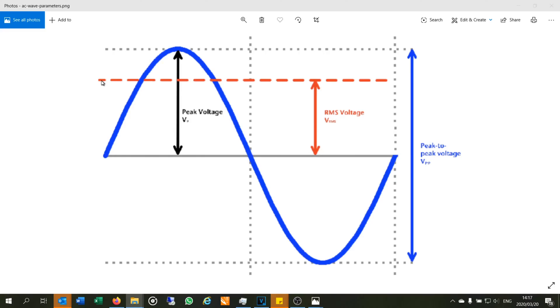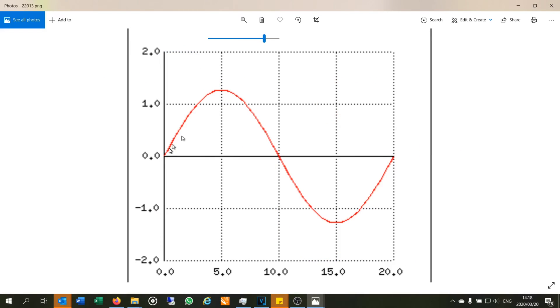Usually when we specify voltage we talk about the root mean square value, which is RMS. In this country, South Africa, we call it 230 volts — that's the RMS value. When they say it's a 220-volt socket, a 230-volt socket, or 110 volts, they're talking about the RMS voltage, not the peak voltage. The last thing I want to bring to attention is the curvature of the wave — it follows a sinusoidal shape. That's also very important, because what often happens when you load up the generator is it becomes a distorted waveform.